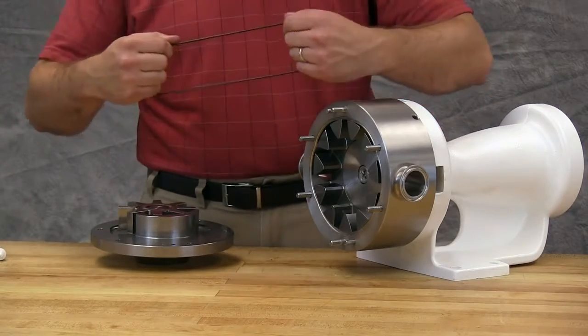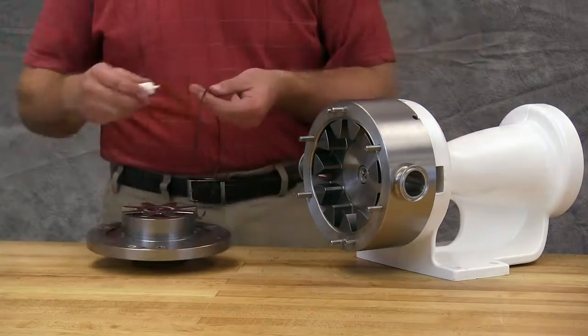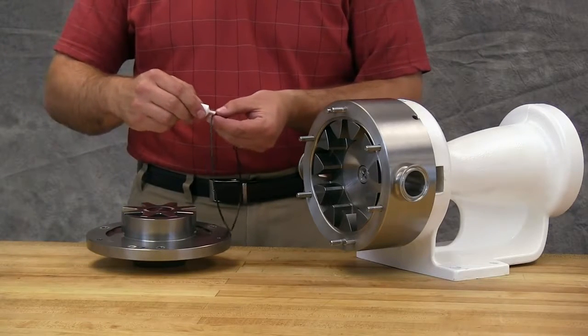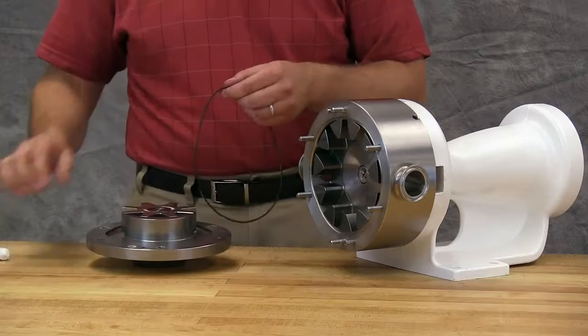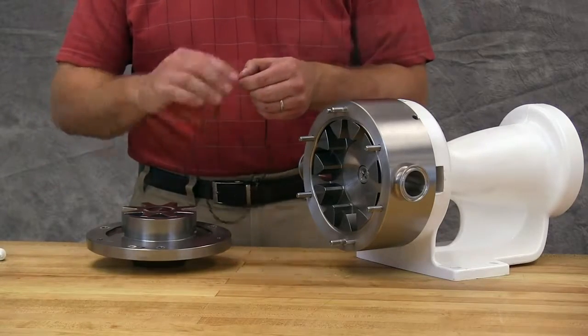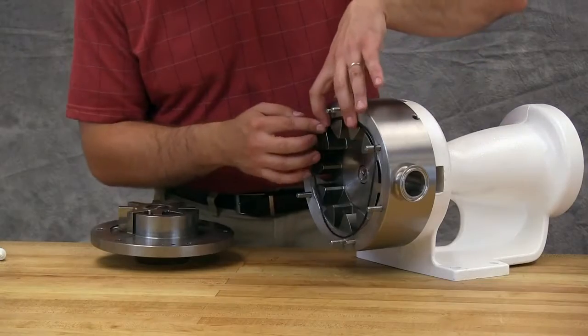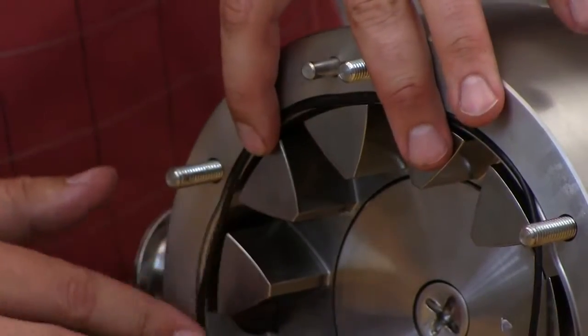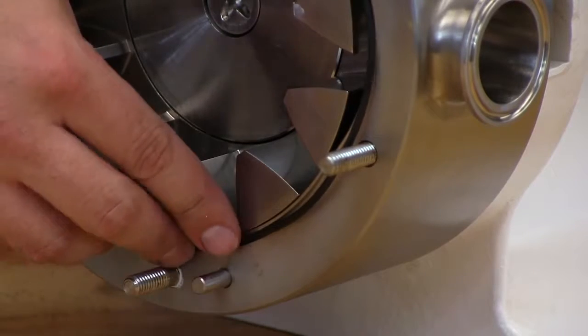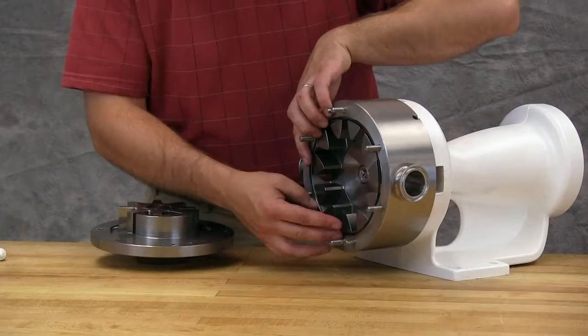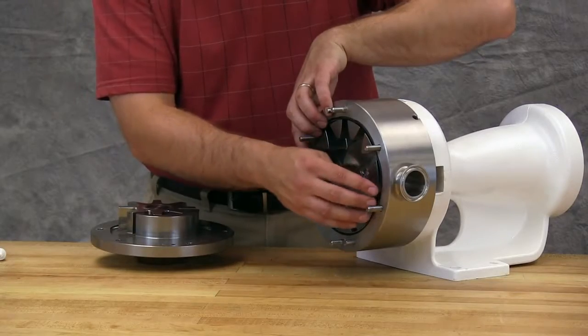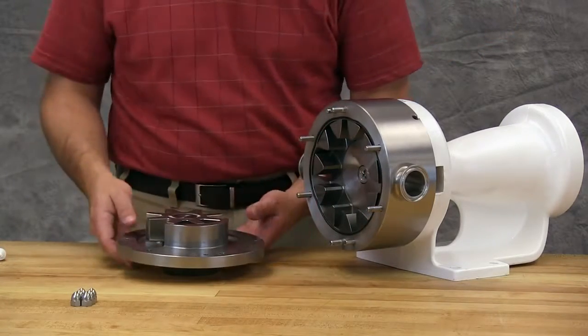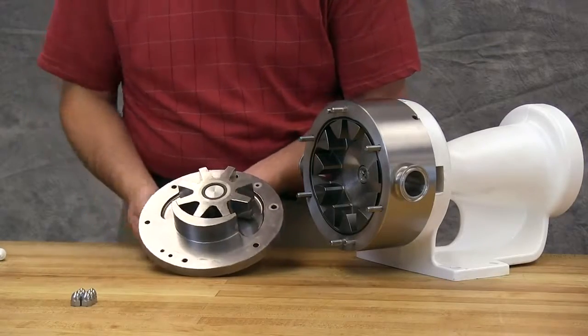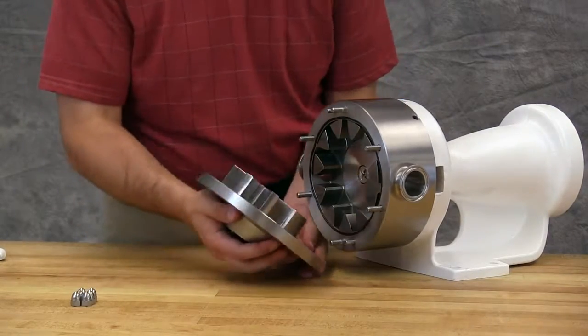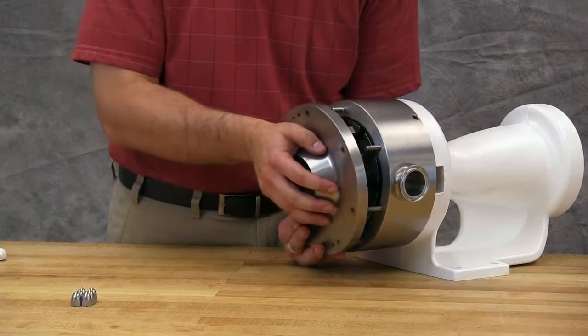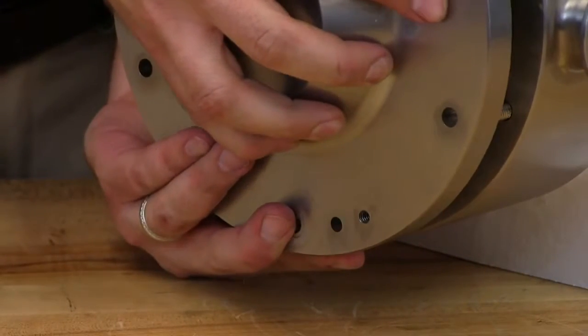The head O-ring may need to be stretched to fit onto the casing. Lubricate the head O-ring to assist with its installation. Install the head O-ring onto the casing. Use the head alignment dowel pins to ensure proper assembly of the head. When installing the head, make sure the idler pin, which is offset in the head, is positioned equal distance between pump port connections to allow for proper flow of liquid through the pump.